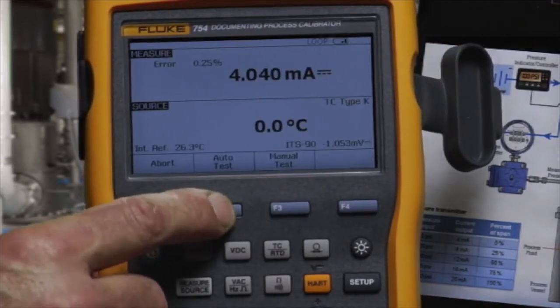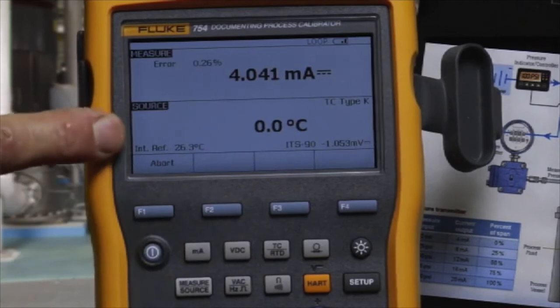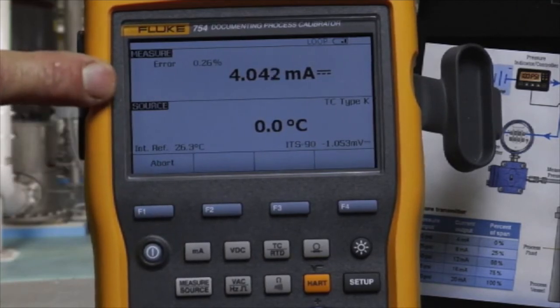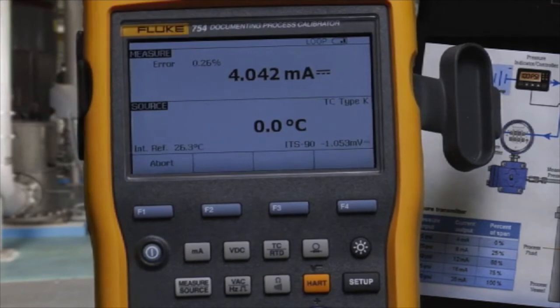Select auto test. The calibrator will apply the 0 percent temperature input, measure for 4 milliamps and calculate for error percent of span.